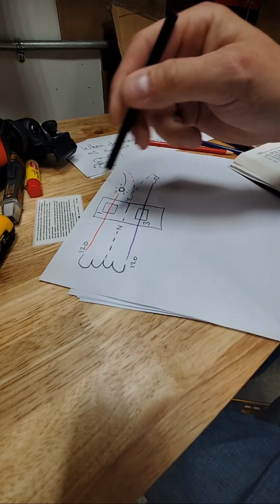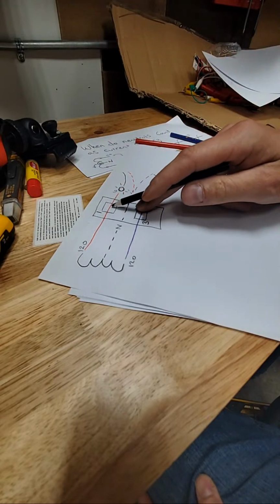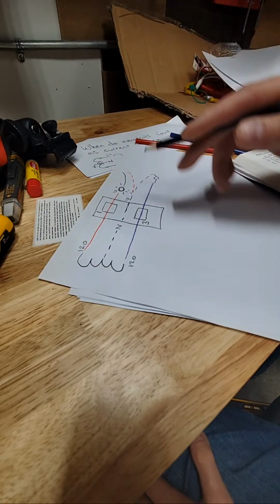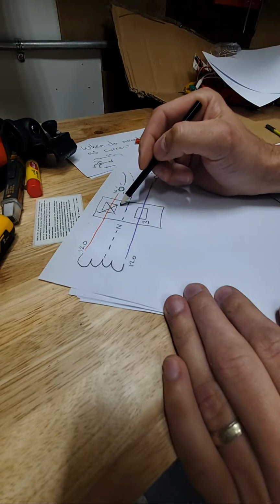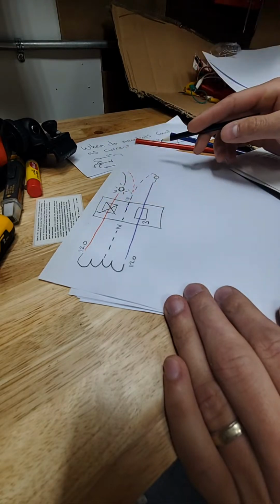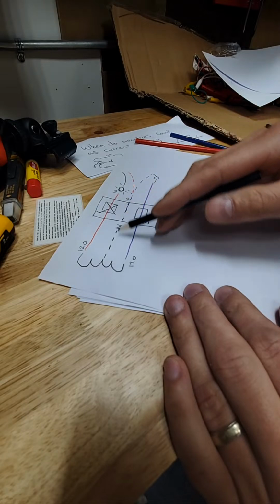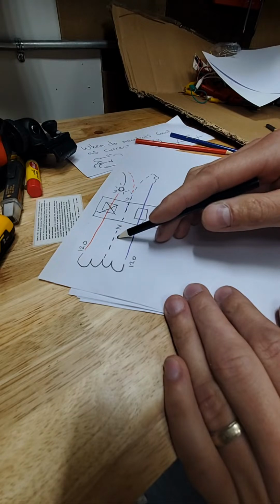We're just going off of whatever, okay? Circuit 1, which would usually be black, and circuit 3, which would usually be red, I know. If we turn off this one breaker here, this is off now. This breaker is still on, so you're still pulling 10 amps. So now this neutral is current carrying.